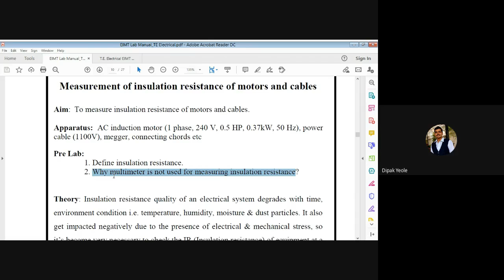Now we move to the theory, related to insulation resistance. The quality of insulation resistance of an electrical system degrades with time, because the insulator loses its property due to environmental conditions like temperature, humidity, moisture, and dust particles. It is also negatively impacted by electrical and mechanical stress. So it becomes necessary to check the insulation resistance of equipment at constant regular intervals.